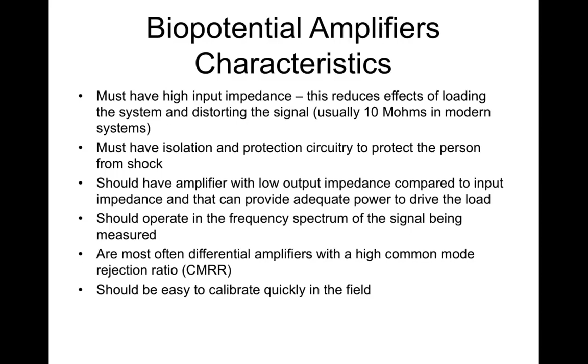Finally, from a practical point of view, you have to realize these instruments are not used by people with PhDs in engineering, they're used by clinicians. The people who work on these systems are generally trained as technicians in the field, not engineers with PhDs. When equipment breaks, there's usually high demand that it be repaired or calibrated as soon as possible. So calibration and repair need to happen quickly, in the field. You don't want to have to send your ECG machine back to the manufacturer for repairs. It needs to be something a well-trained technician can do, and calibration, preferably, something the ECG tech themselves can do.